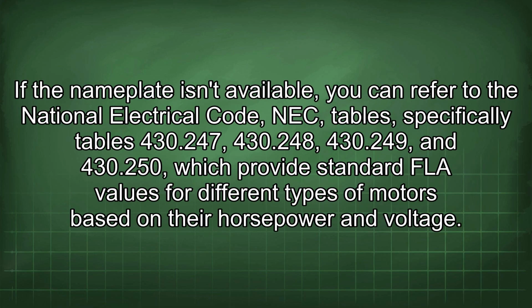If the nameplate isn't available, you can refer to the National Electrical Code, NEC, tables, specifically tables 430.247, 430.248, 430.249, and 430.250, which provide standard FLA values for different types of motors based on their horsepower and voltage.